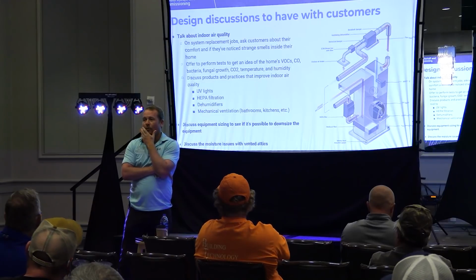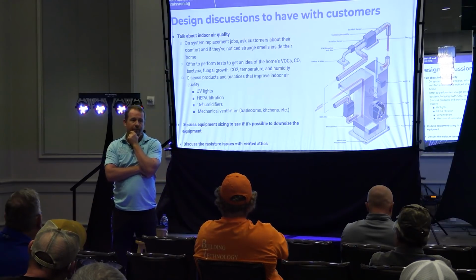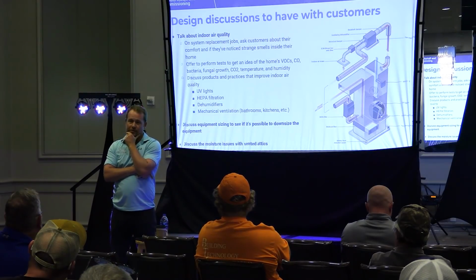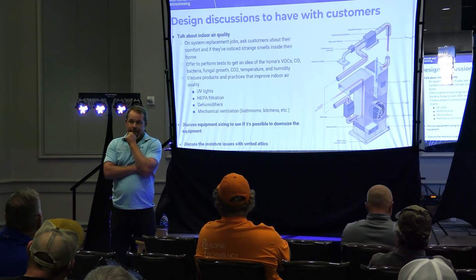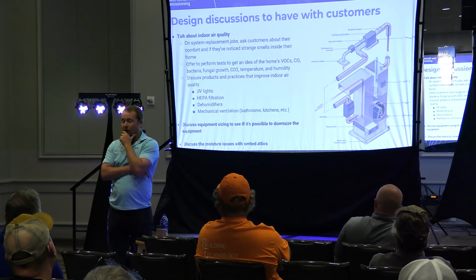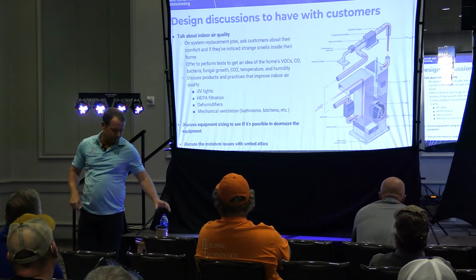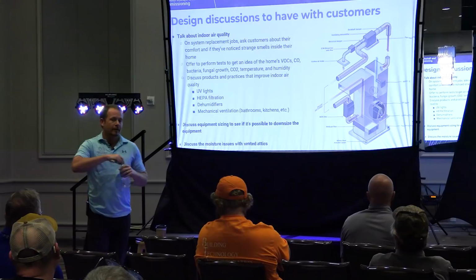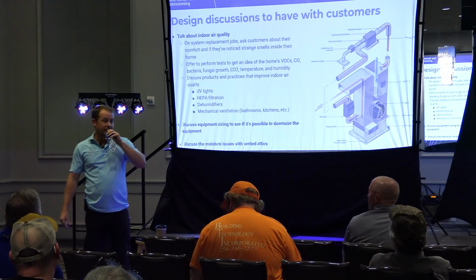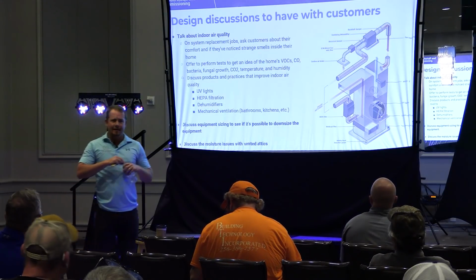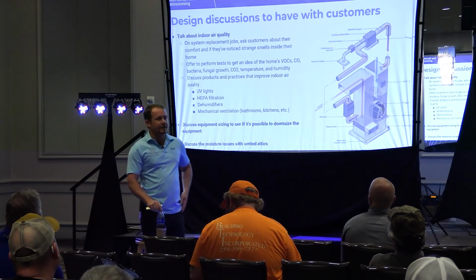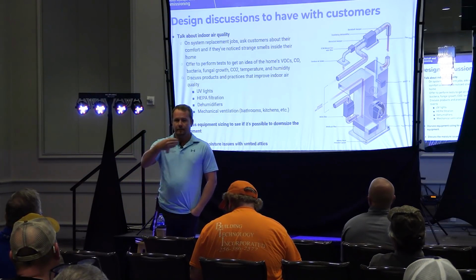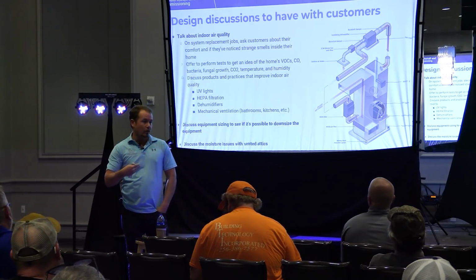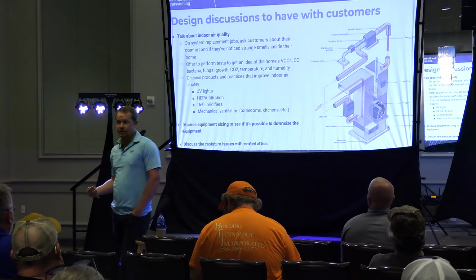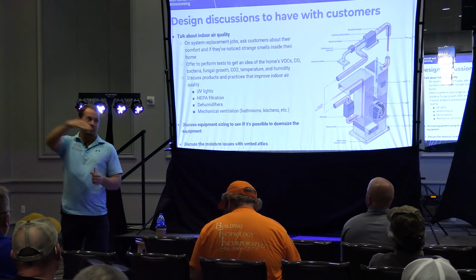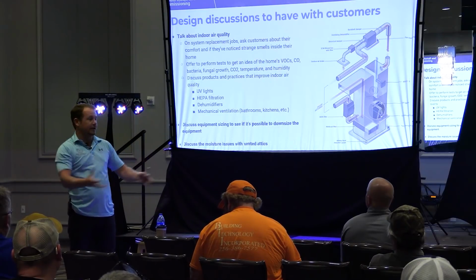So why does mold growth result from people setting their temperatures lower in the space? Lower dew point - lower dew point on the outside of your ducts, lower dew point on everything, on the walls and the inside. You'll see cases so bad that you'll actually begin to get mold on the inside of walls that aren't even related to the air conditioning, just because maybe there's a vent blowing nearby, and you'll start to get mold on the wall there.